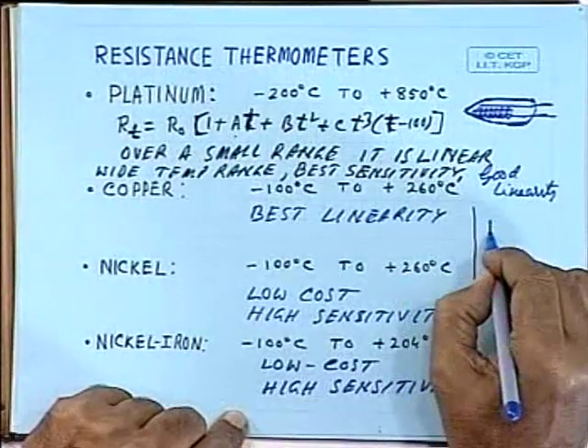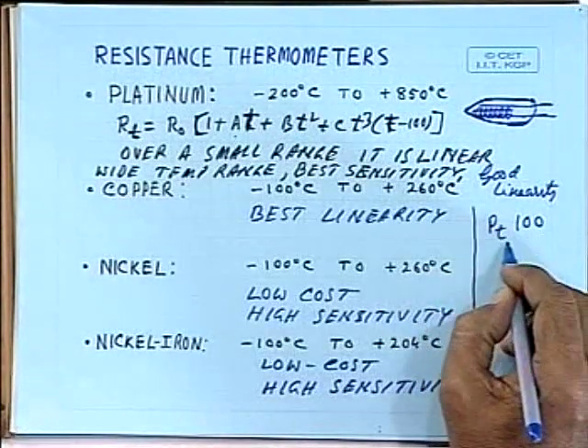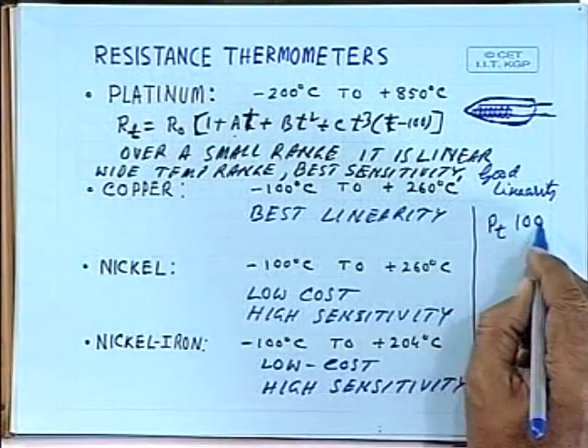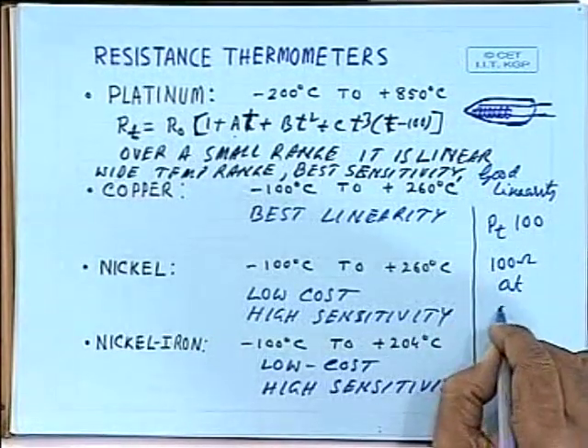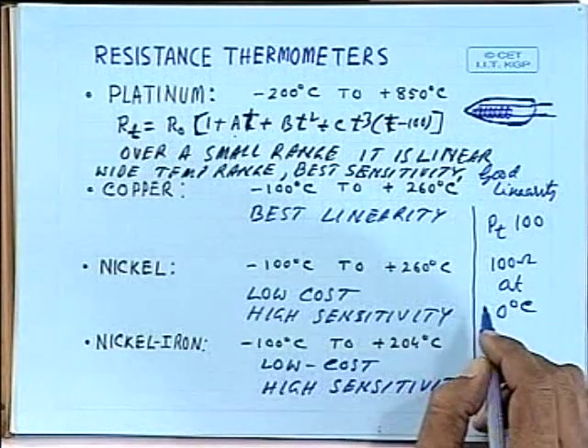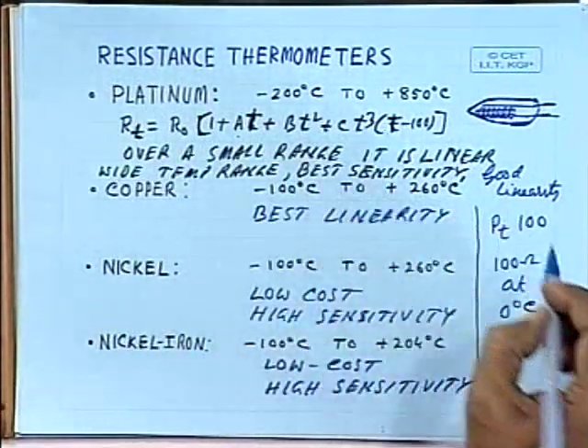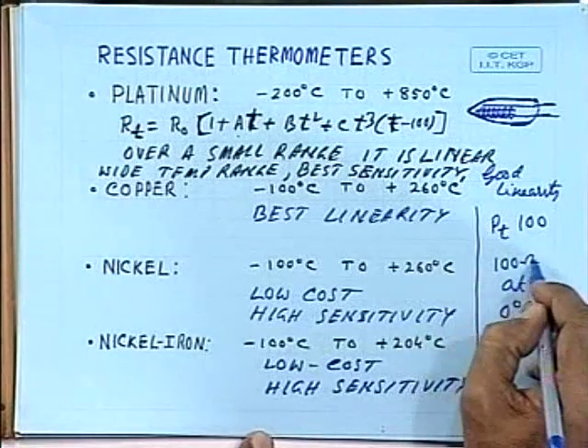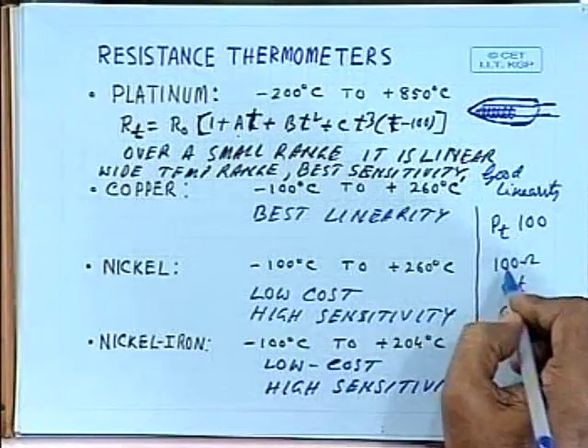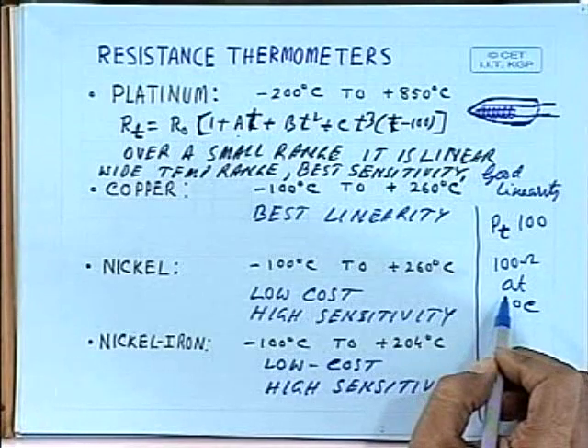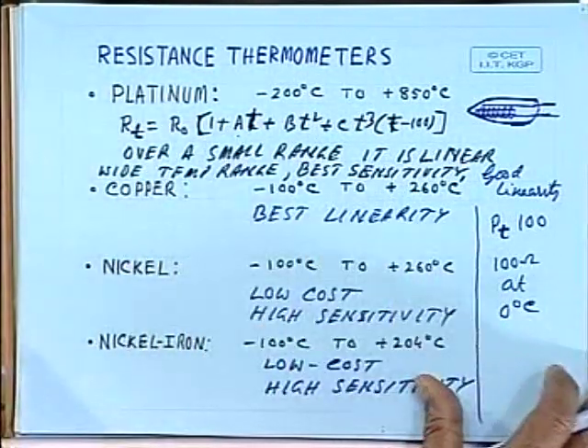The most popular is the platinum resistance thermometer. For example, the PT-100 is a widely-used, commercially available device. PT-100 stands for a resistance of 100 ohms at 0°C, and as temperature changes, the resistance changes according to the formula. To accurately measure the change in resistance, you will require a bridge arrangement, which will be discussed later under signal conditioning circuits.